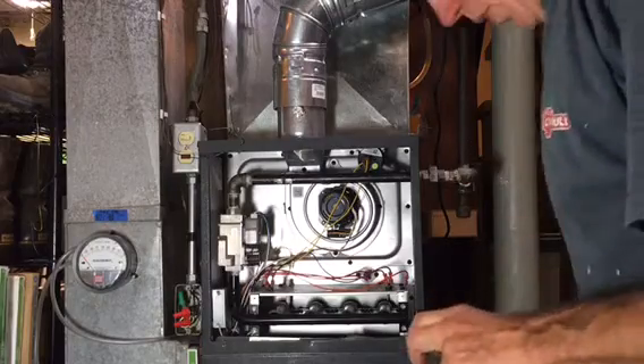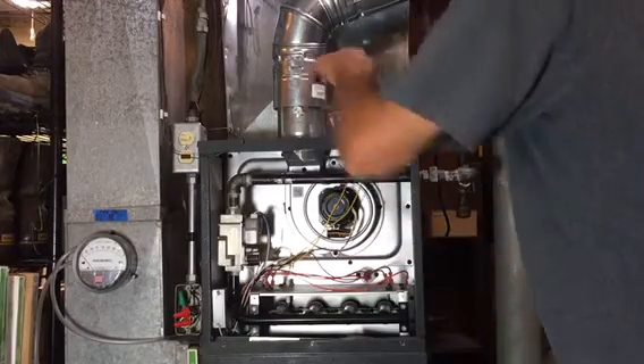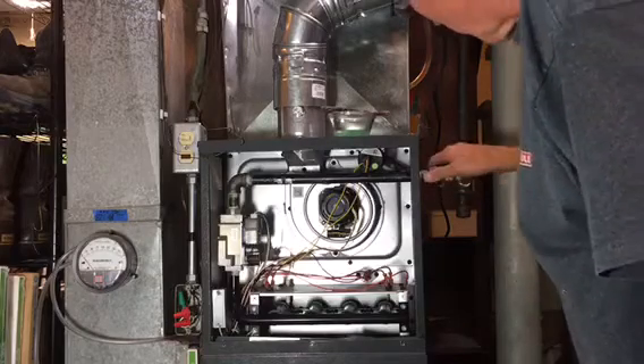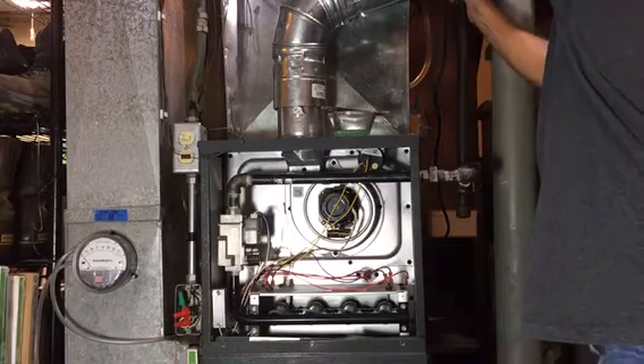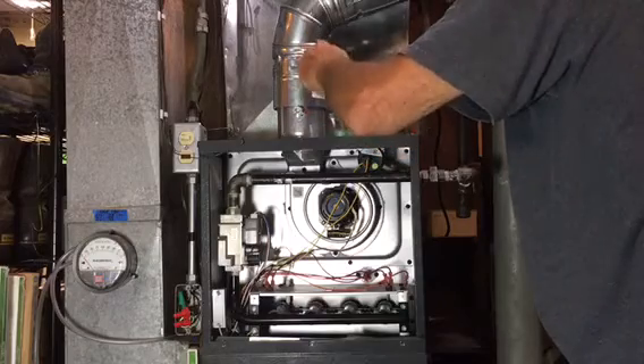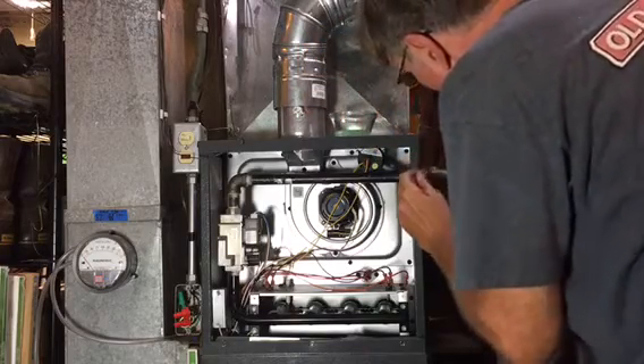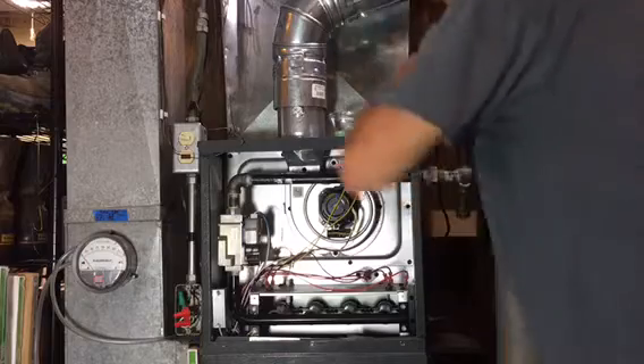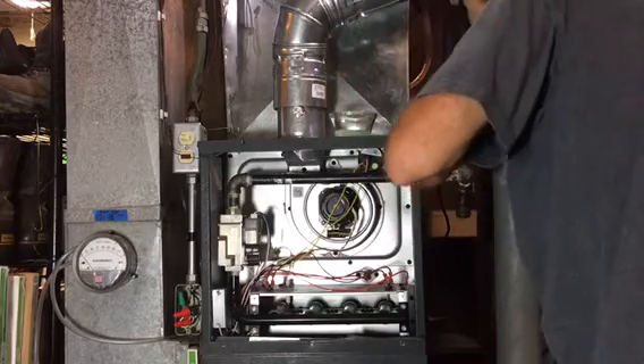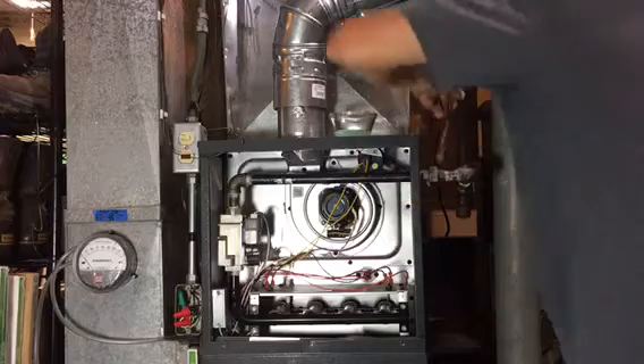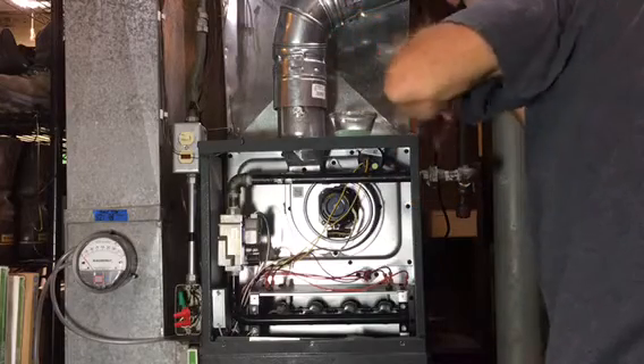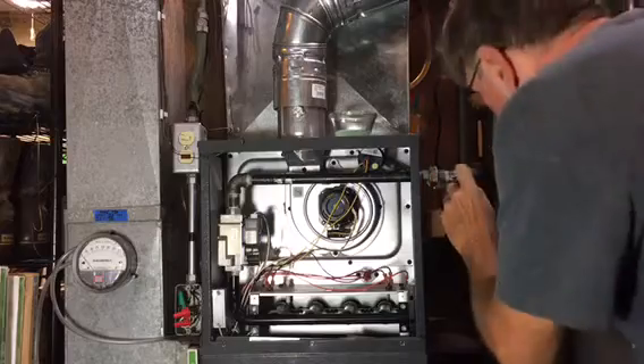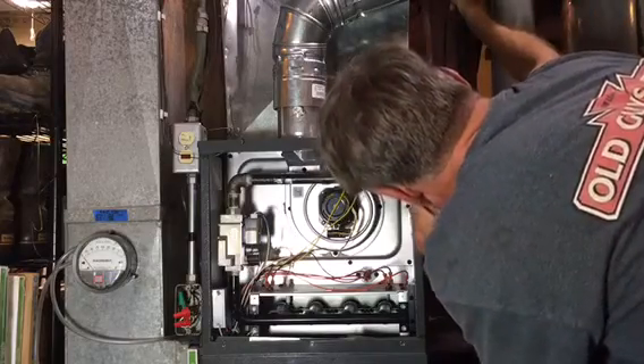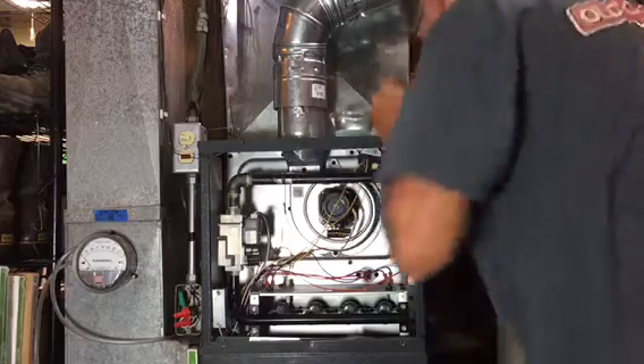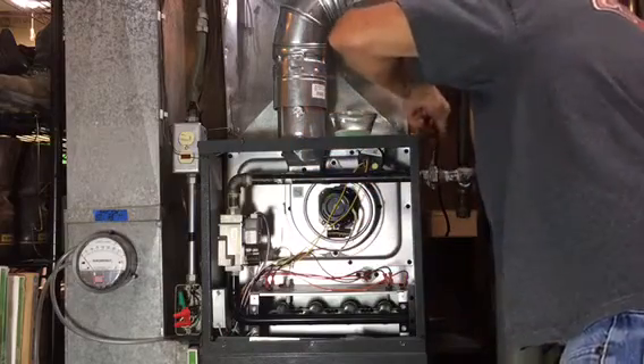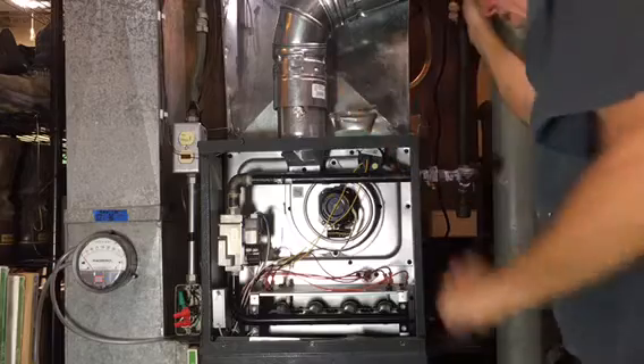Okay, always when reestablishing connections, one should check for leaks. So the valve's off, I tighten this up. I'm going to open it up again. And we're just going to take a little soapy water in this paintbrush and put it around on both sides. Any gas bubbles would be apparent. Common low-tech way of testing, and I am not seeing anything. You want to look around all sides. Okay, so I think we're good.